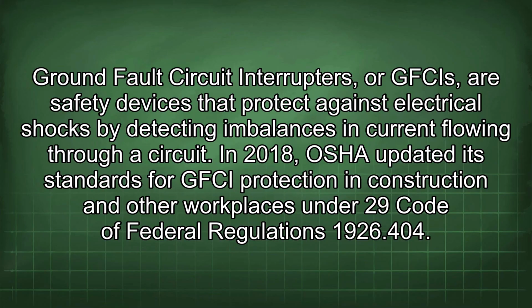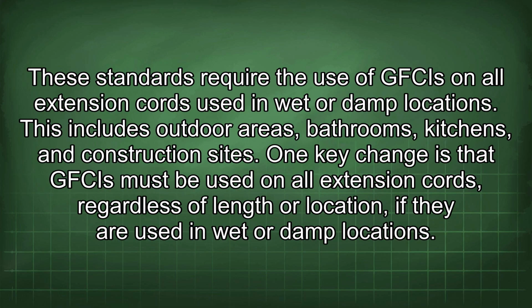Ground fault circuit interrupters, or GFCIs, are safety devices that protect against electrical shocks by detecting imbalances in current flowing through a circuit. In 2018, OSHA updated its standards for GFCI protection in construction and other workplaces under 29 Code of Federal Regulations 1926.404. These standards require the use of GFCIs on all extension cords used in wet or damp locations.